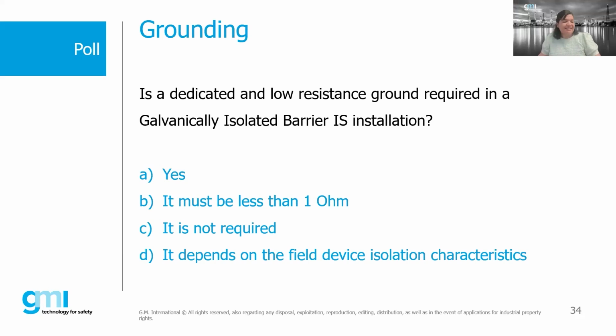So you want to explain this question, Bob? Sure. The answer is, it's not required, because a low resistance ground for galvanically isolated devices is not required. It is required for Zener barriers, so it's a bit of a tricky question. If it is required, it must be less than 1 ohm resistance, which is true, but that doesn't apply to galvanically isolated devices. It also depends on the field device isolation characteristics. But the correct answer is: it is not required.